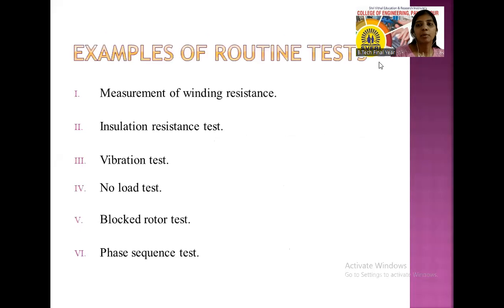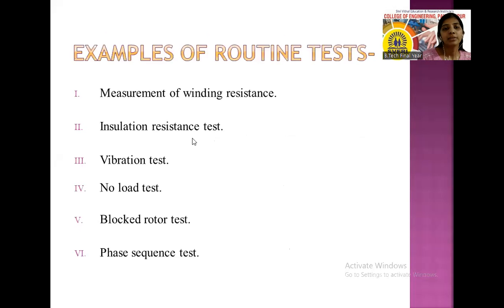So which type of routine test can be done? Measurement of winding resistance, insulation resistance test, vibration test, no load test, blocked rotor test, phase sequence test. Such type of tests can be carried out on each and every machine manufactured in the industry. This is called the routine test.